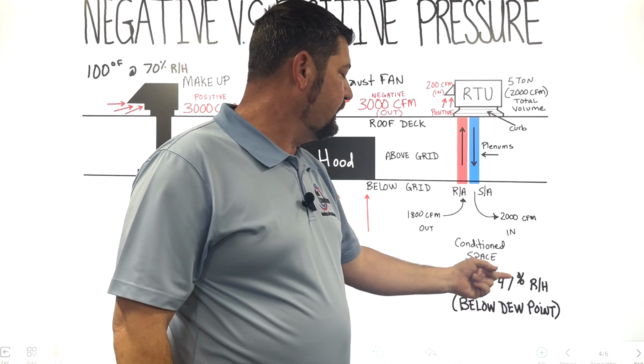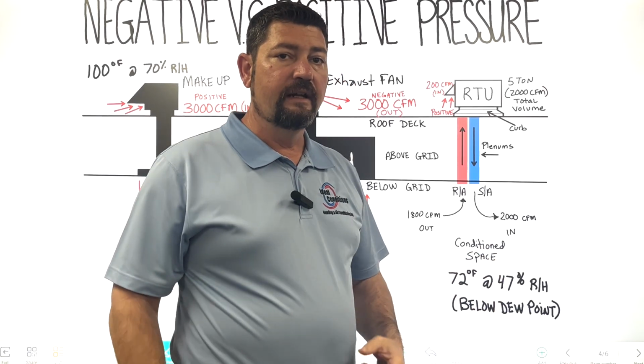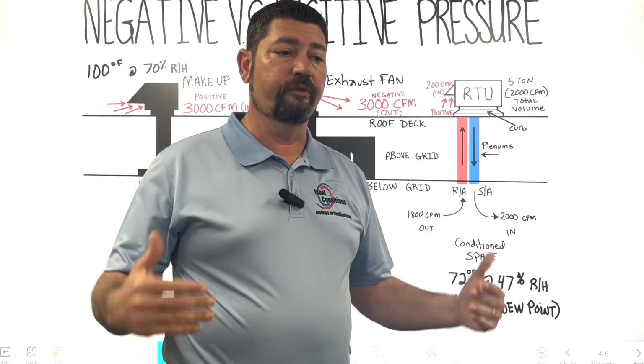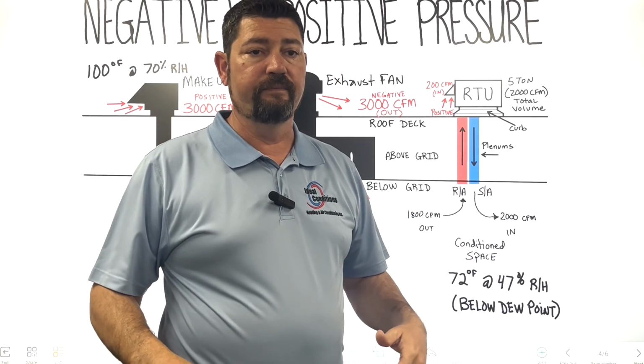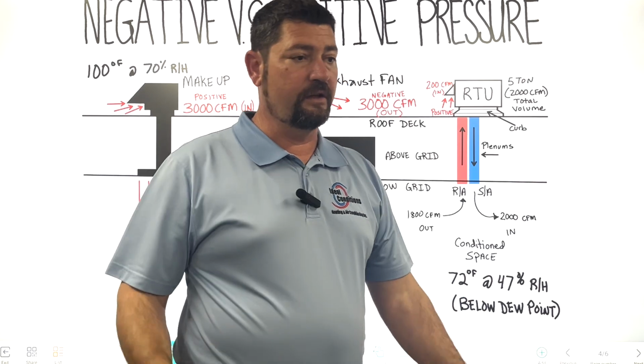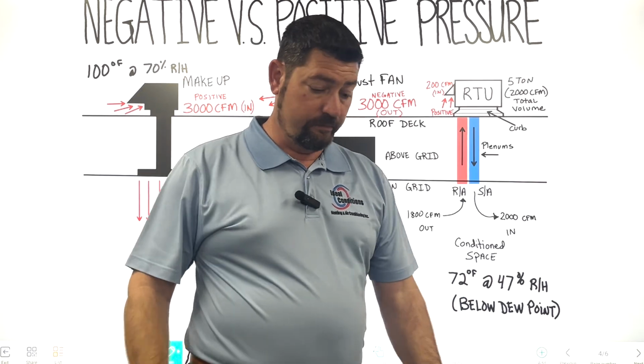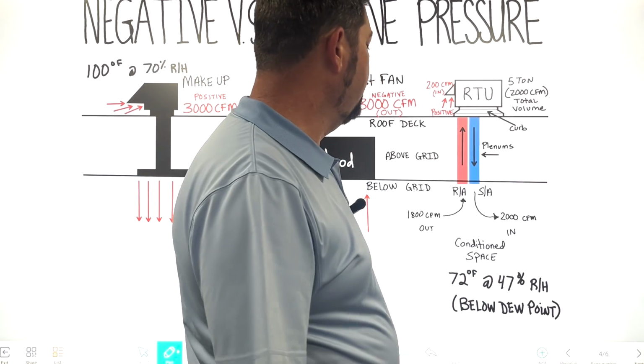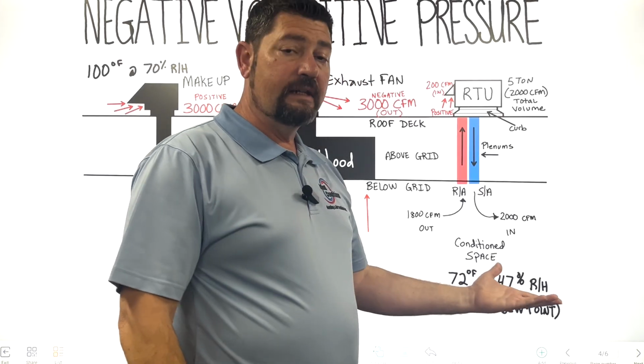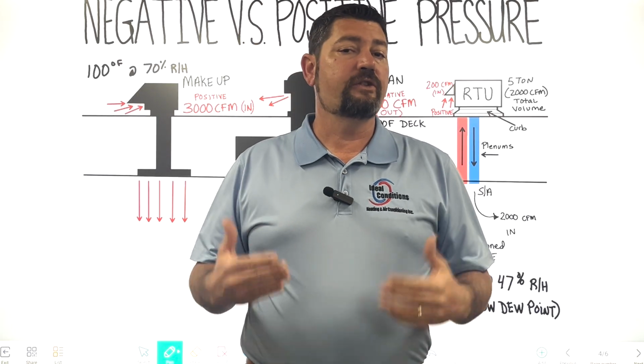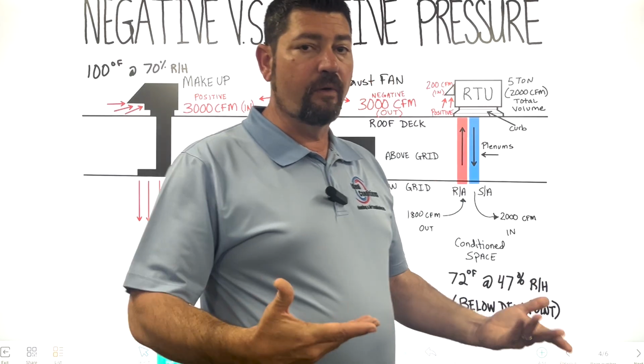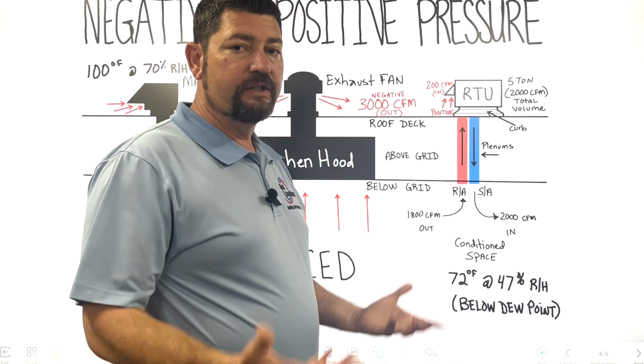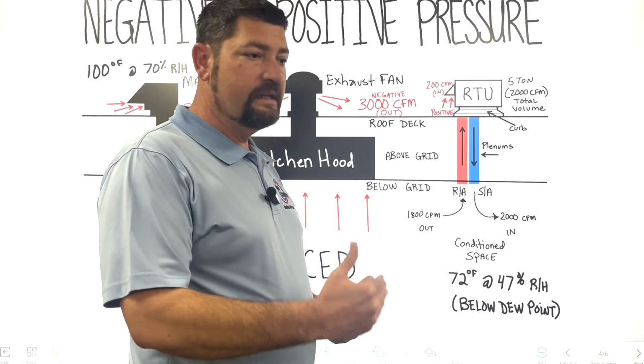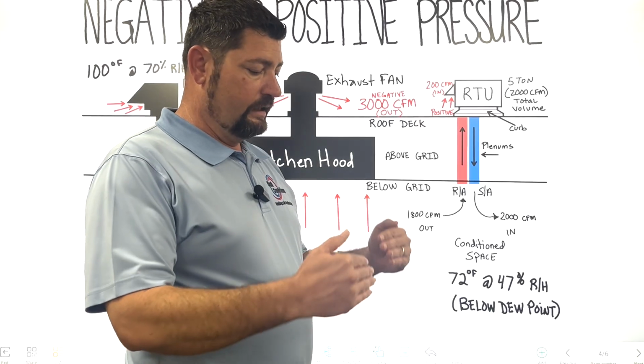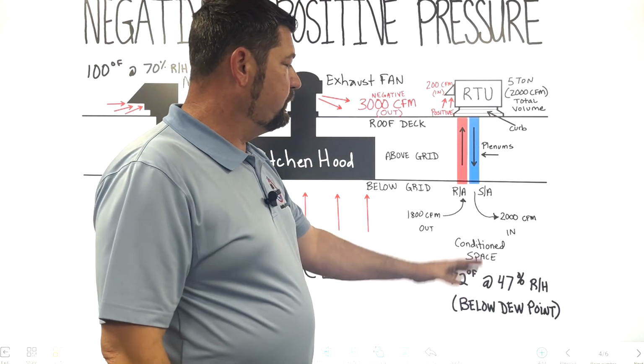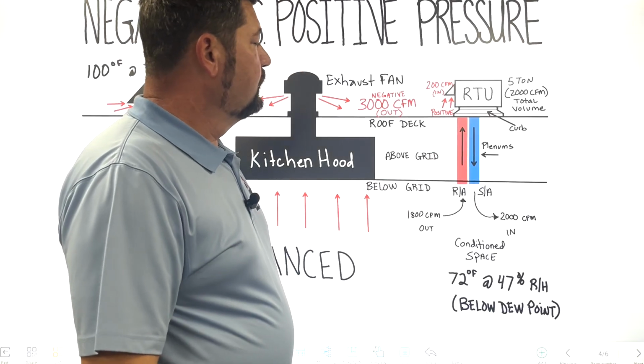And when that humidity spikes up and that temperature is still sitting over here, that humidity is going to collect on everything cold. So now vents are going to start to sweat. People are going to start putting trash cans out. Customers are going to get water dripping on their plate of food, their head, their clothing. They're going to be upset about that. Very common. And then technicians may not understand why there is water on the vents. And very simple, it's the humidity that's in the air. It's reaching dew point, right? Because your humidity is high and your temperature and that humidity are very close, and you're just reaching a dew point, and water's going to fall.